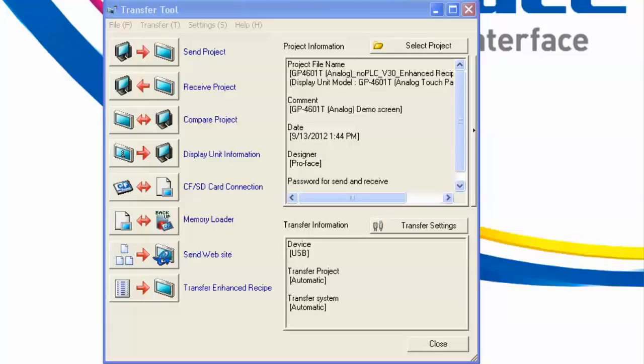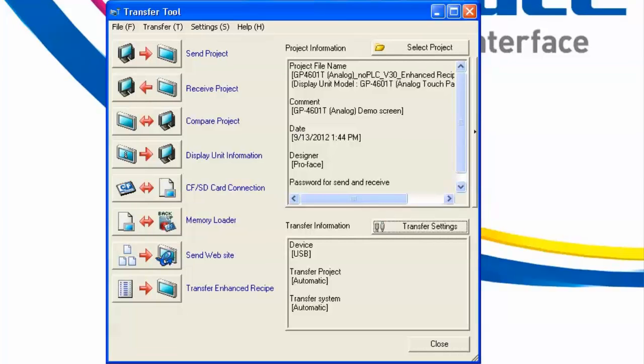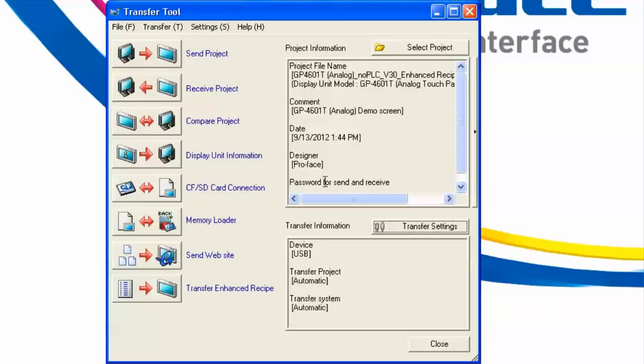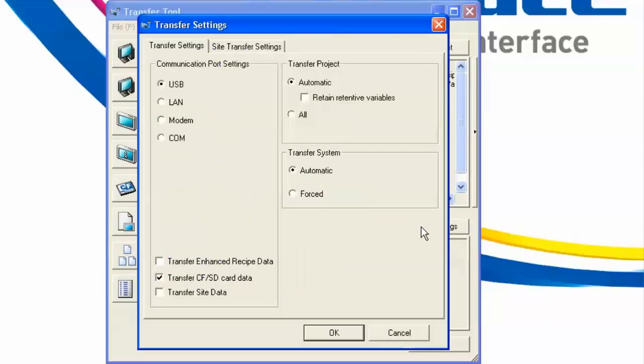Two: we need to transfer the website itself down to the HMI. To send this project to the HMI, we use the Send Project button at the top or the hyperlink next to it. Down here we have the Send Website button, which allows us to manually transfer the website whenever we press it.